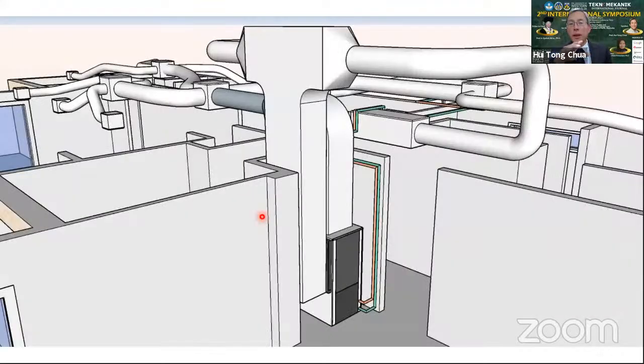So this is a perspective view of the ducting layout in and surrounding the ground source heat pump here. You can see that the plumbing system runs through the attic. The green pipe here supplies groundwater to the ground source heat pump, whereas the brown pipe returns the groundwater back underground, once again routing along the attic, which then leads out of the property and goes back to the backyard where the doublet system resides.